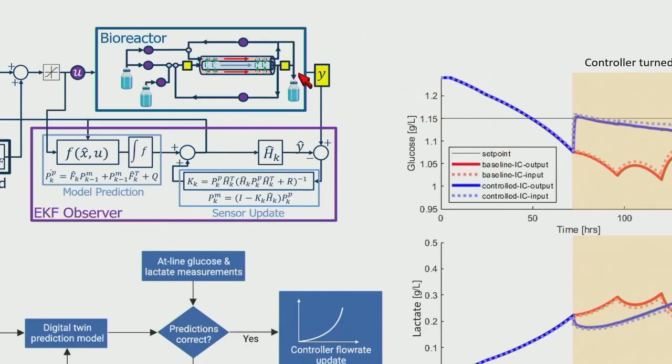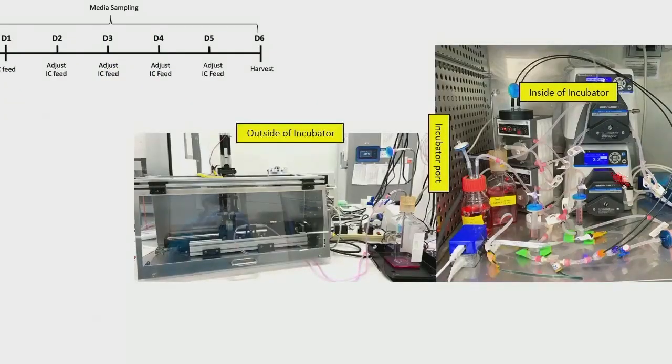What we do is that we have multiple sensors around the bioreactor. It monitors in real time, and then we create a mathematical model that models the glucose consumption rate, the measurement rate, the infusion rate, and we continuously infuse media and glucose or lactate, or for that matter, any other cytokines or growth factors, and try to keep very steady bioreactor conditions over time. So this is a feedback control. We sense, we decide, we control automation platform. This is how it looks. This is the non-fancy engineering version of it.